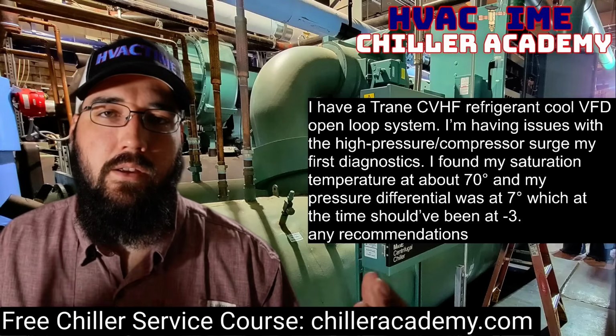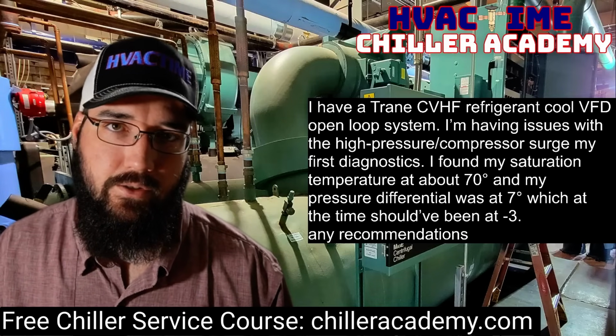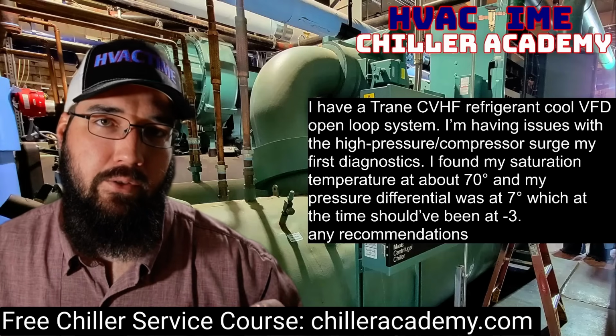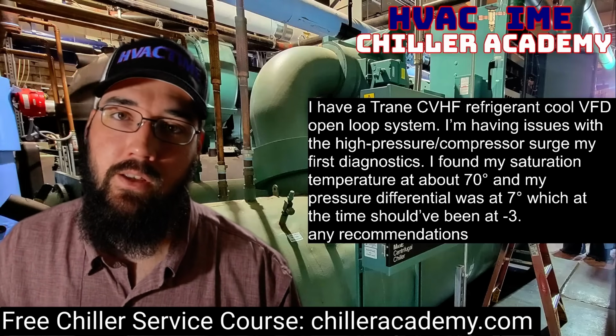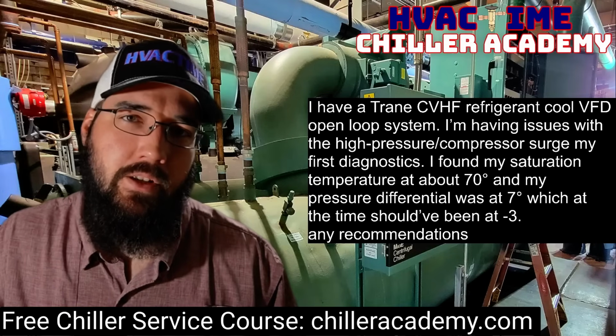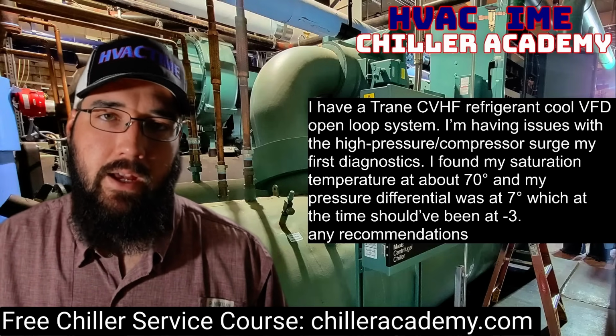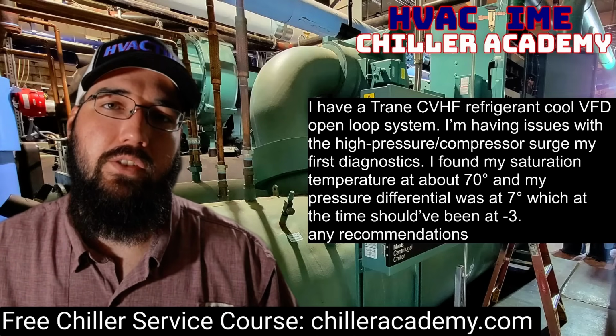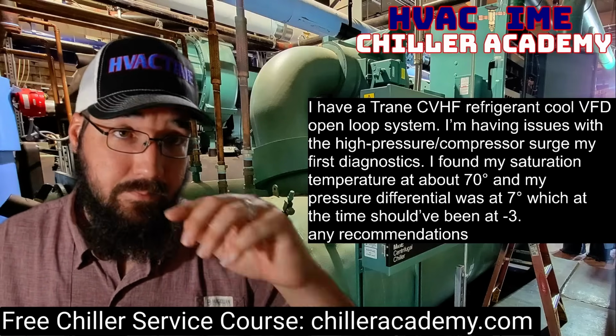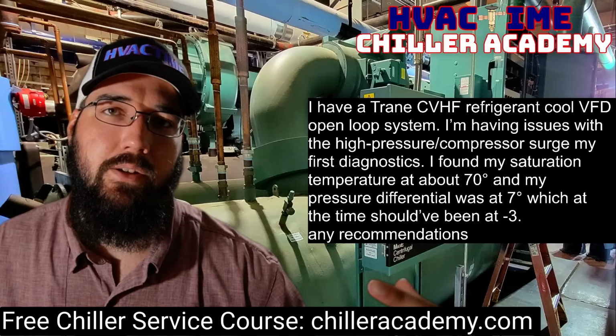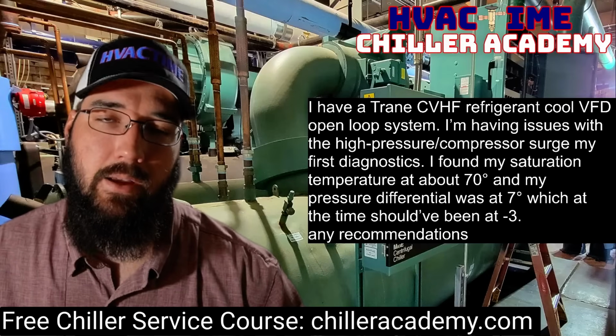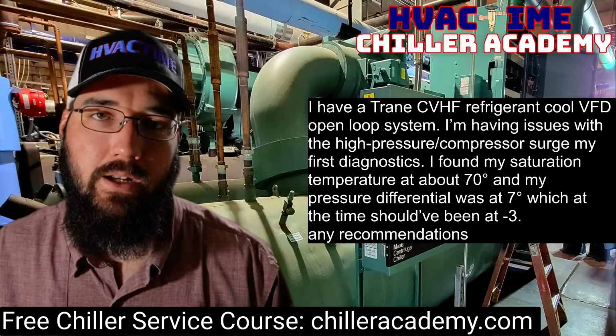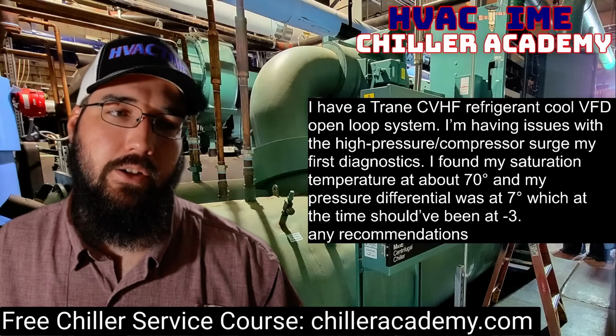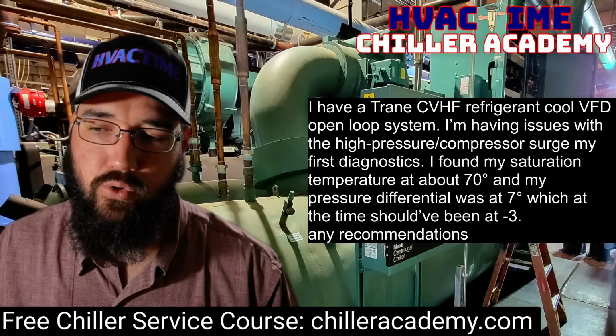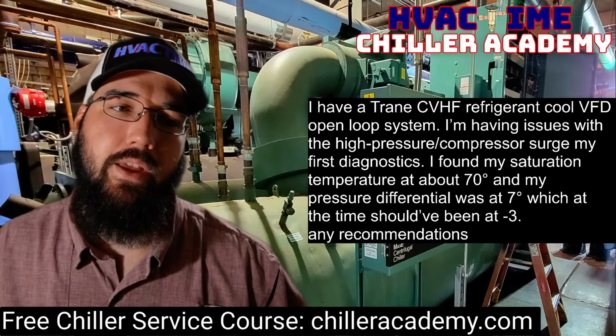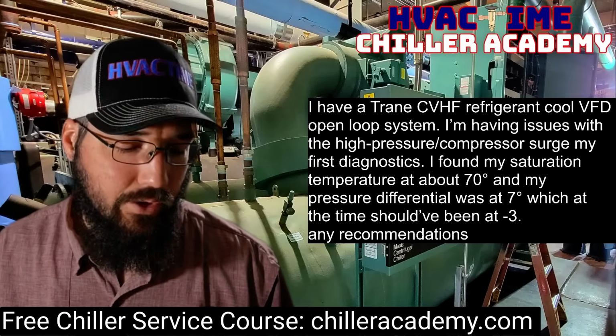Keep that in mind. You don't specify what region you're in or what your climate conditions are like. Maybe this is a fresh seasonal startup, which at that point, it's not a good thing, but it's not necessarily abnormal. What's important though, is if you have a machine like that and you are doing a seasonal startup for the warm season, you really want to plan to do that pre-purge ahead of time, and specifically using that portable purge system to do that, not waiting until the chiller tries to turn on and destroy itself. Now that's up to the customer, right? We don't actually have control over something to that detail. They've got to decide to allow us to come in and do that routine seasonal thing.